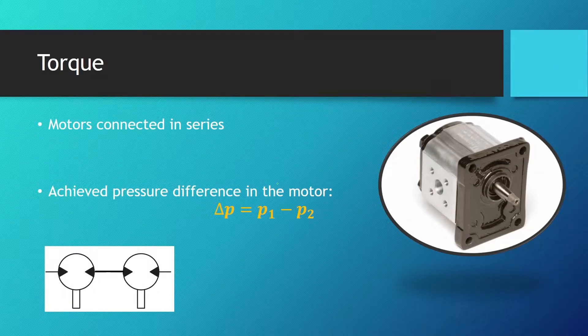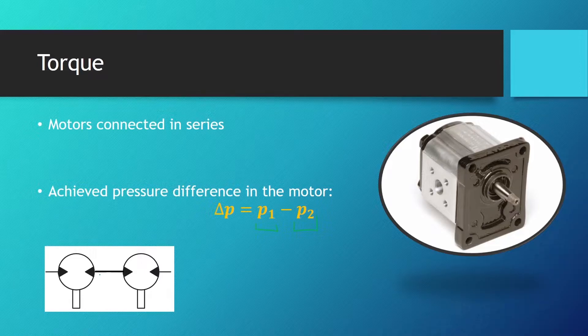Now if you remember from when we talked about pumps, on the inlet side of the pump we have under pressure, we have vacuum, and on the outlet side we have overpressure. With hydraulic motors however, on the inlet side we have an overpressure P1 and on the outlet side we can also have an overpressure P2. In this example we hooked up another energy consumer in series with the motor, so for example two motors. P1 is an overpressure and P2 is also an overpressure but it's a smaller pressure than P1 because part of the pressure was consumed by the motor.